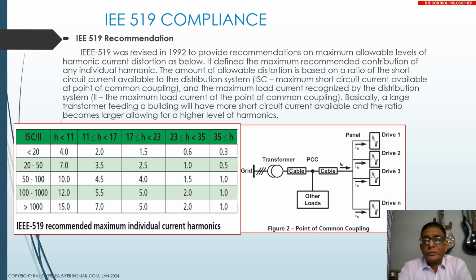In all, what this fellow means to say is it depends on the transformer. You have a bigger transformer and smaller VFDs. How much current do the VFDs plus the other loads at the point of common connection take up with respect to the short circuit current of the transformer? So if you see 100 to 1000, it is a very small fraction of the transformer's capacity. So with a larger capacity transformer and VFD loads that do not amount to much, you can live with a higher amount of distortion.